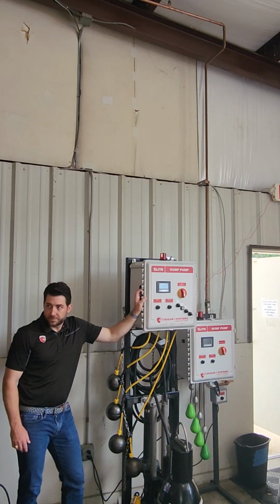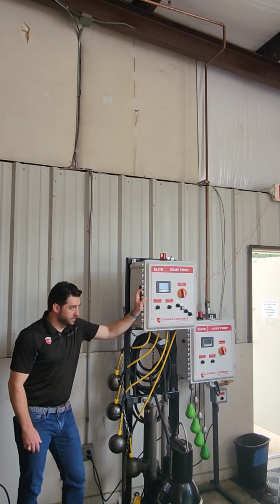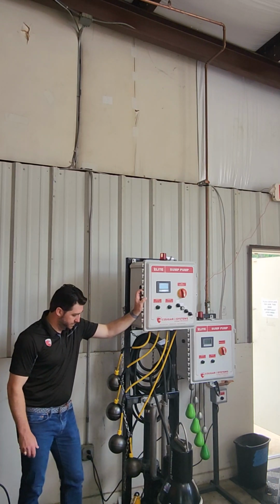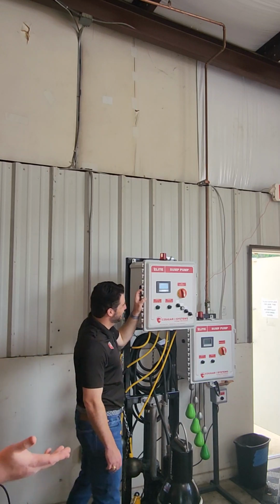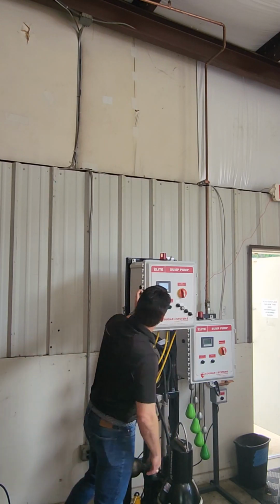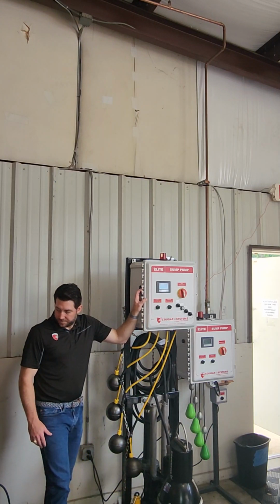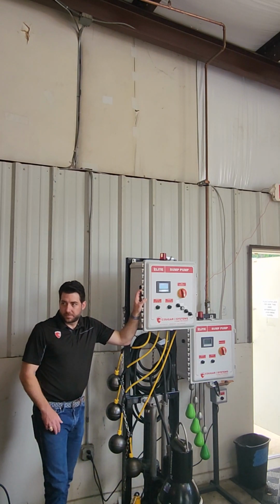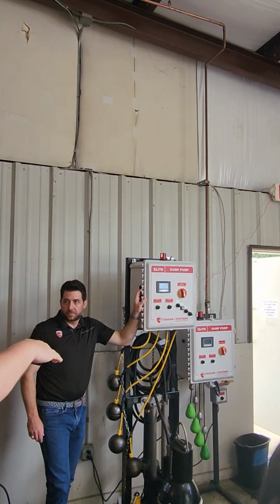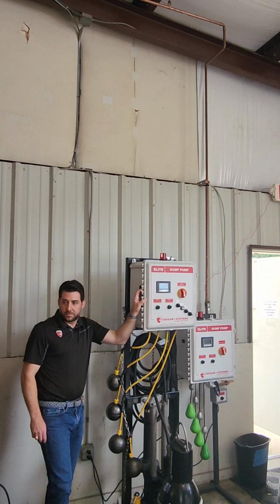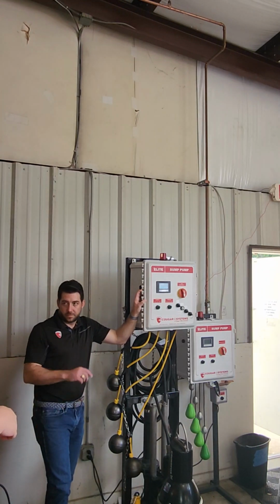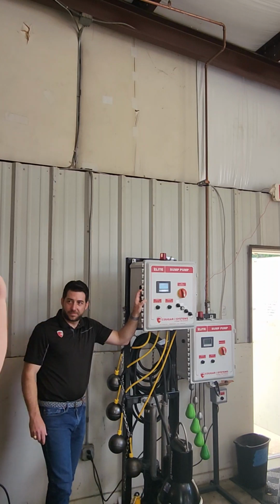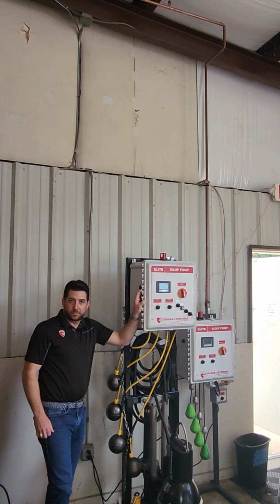If you've got your inlet coming in and your pump's down here, they need to get to at least halfway when they're getting alarmed. Hey, look, your pit's getting full, you need to hurry up and change. And hopefully you've got one of these where it just turns on. Yeah, well, let's hope so. But you know what situations we're dealing with, guys, most of the time. So keep that in consideration with this alarm here. And pump 2, you don't want pump 2 kicking on when you're already up to the inlet. But you need to get it about halfway, a little bit over halfway, to where pump 2 is kicking on. Actually, I'm going to rebut what I just said. You need to be about halfway where everything's running. So if it gets halfway, then we need to hurry up and get that alarm going, and then everything's starting to pump on the second pump.